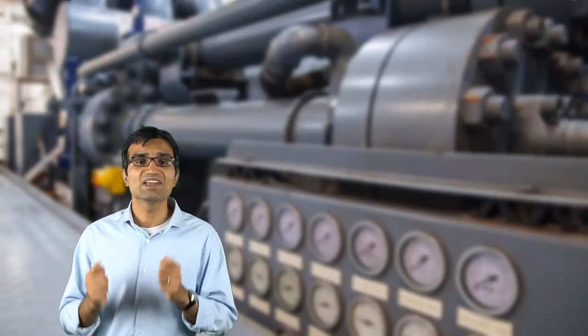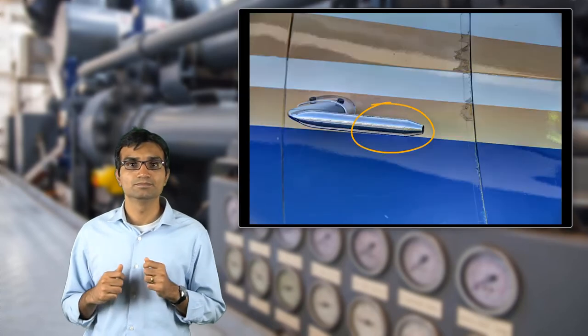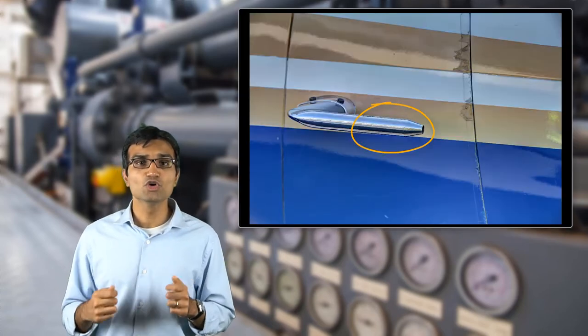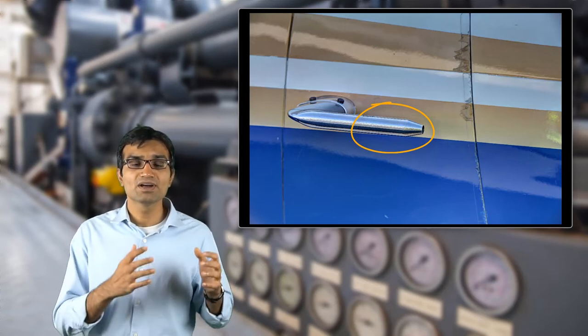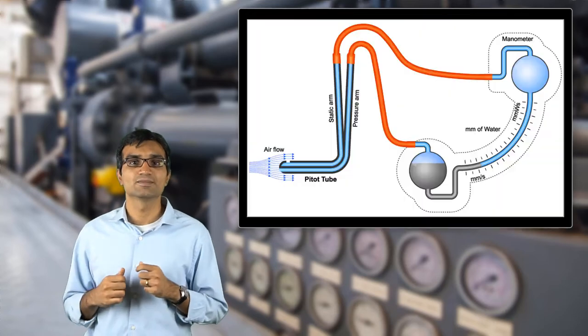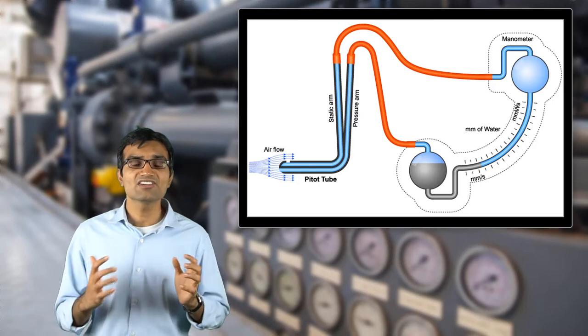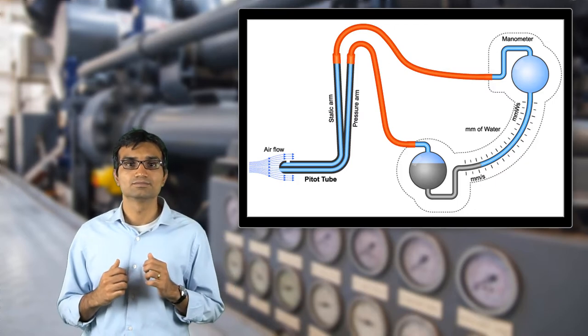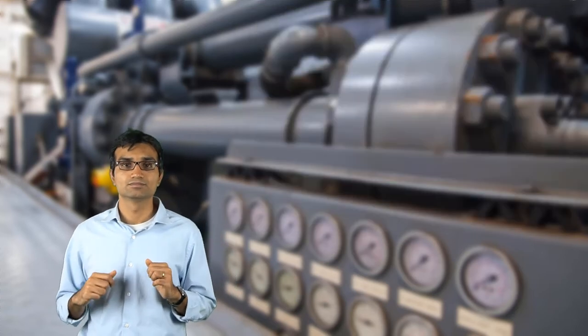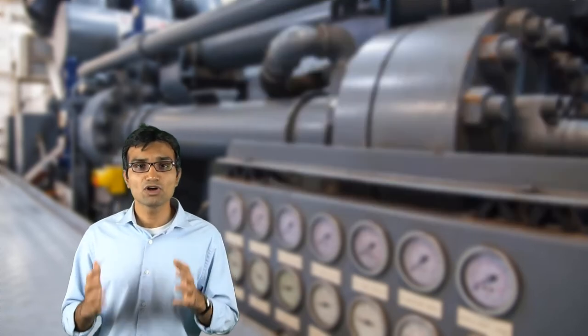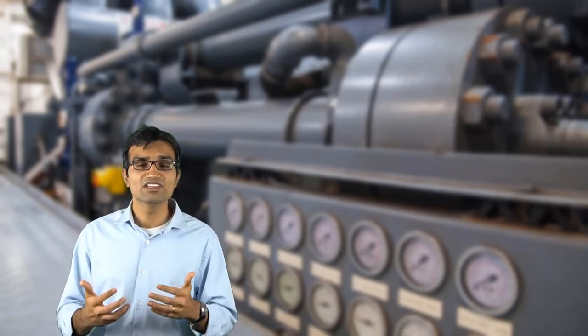The simplest way of measuring the local velocity of the fluid is using a pitot tube. A pitot tube is an L-shaped tube where measurements are taken both on the tip as well as on its sides. The total pressure or stagnation pressure of the fluid is measured at the tip. The static pressure measurements are taken on the side. The local fluid velocity is calculated using these pressure measurements based on Bernoulli's principle.